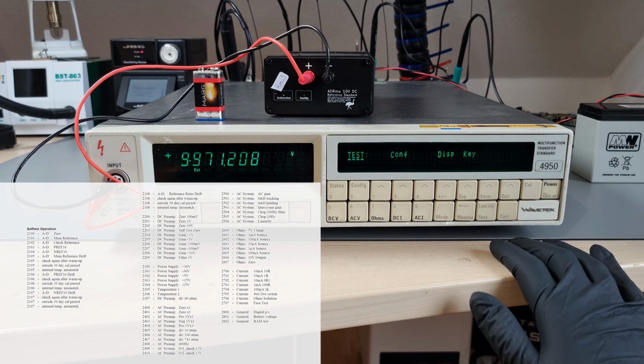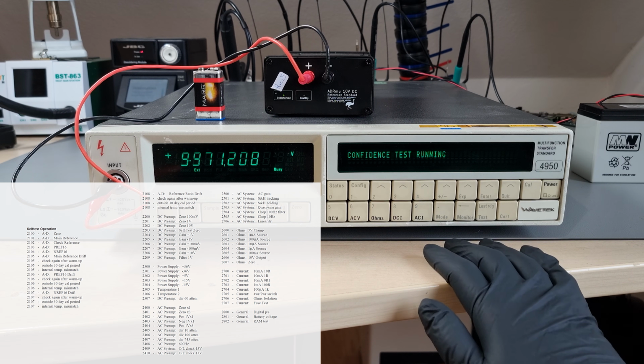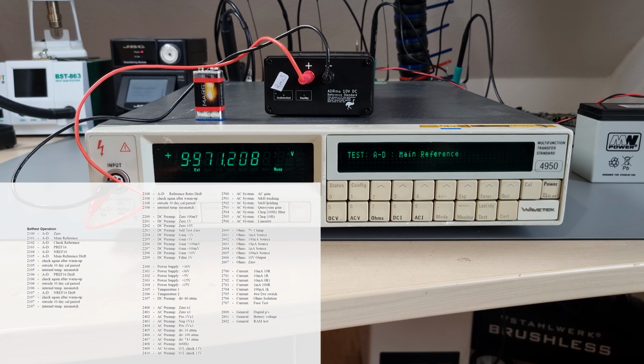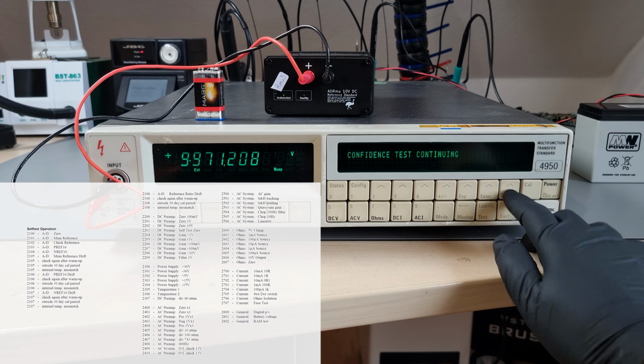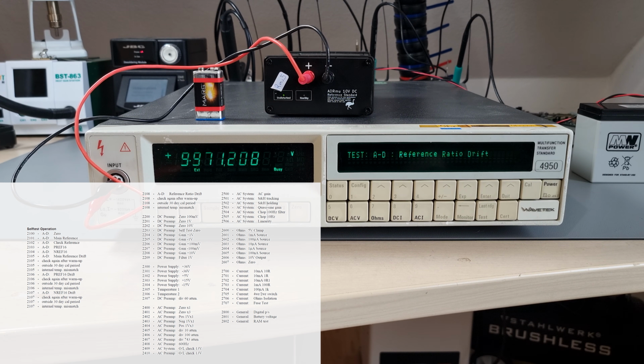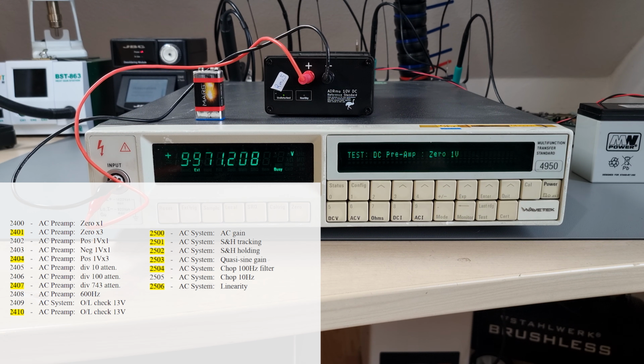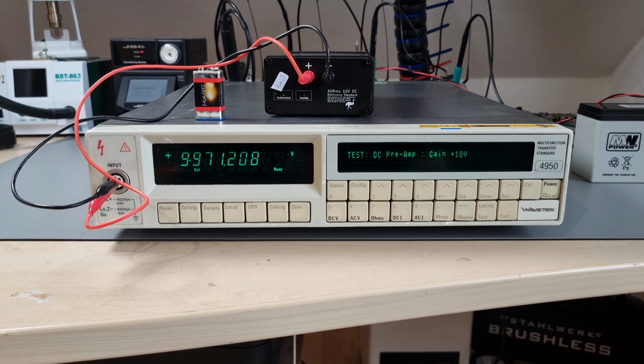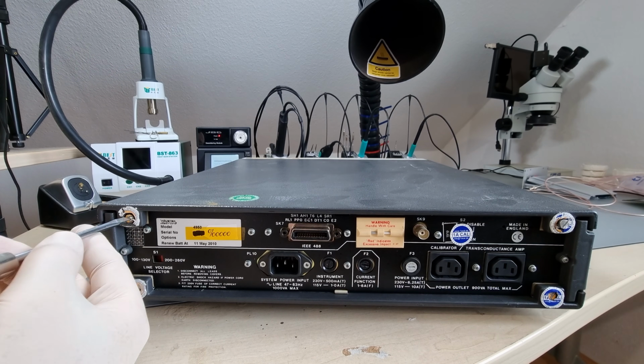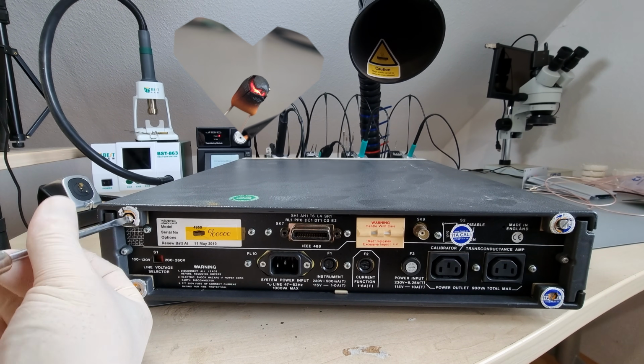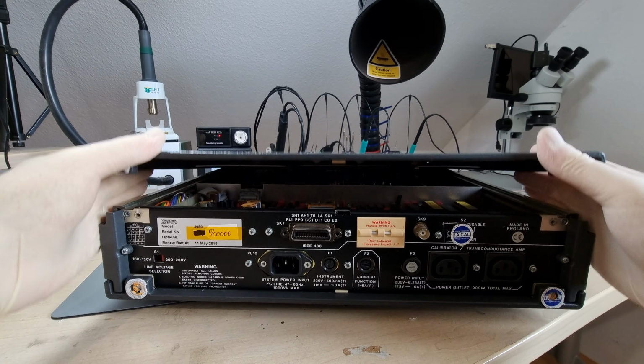This is a fairly sophisticated procedure, testing for things like plausible ADC readings at no input, drift of both of the voltage references in here, state of calibration based on memorized data and a real-time clock. It can even conjure test signals to verify its own AC and DC preamps, those ranges, and currents and resistances too. And sure enough, after a couple of runs I did catch some intermittent errors, mostly in the AC department. Now you could argue, hey, at least it's working sometimes. But nah, intermittent faults are not what I like to see. I like to find big, obvious, crispy problems, removal of which makes everything recover magically. No such luck today, I'm afraid.